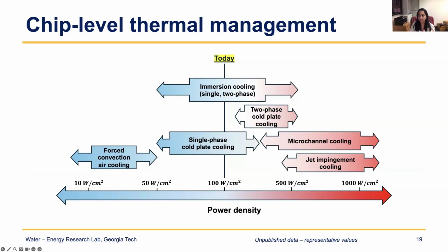And then immersion cooling is still somewhat early stage, not commercially used, but you can do single phase or two-phase immersion using some refrigerants. These typically do not perform as well as water, because the thermophysical properties and latent heat of these refrigerants and dielectrics are much less than water.